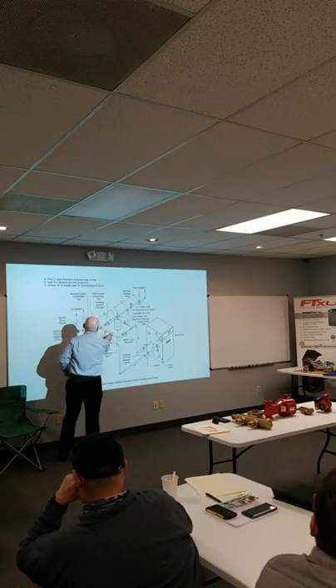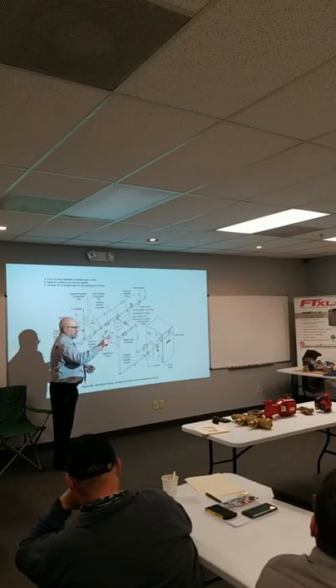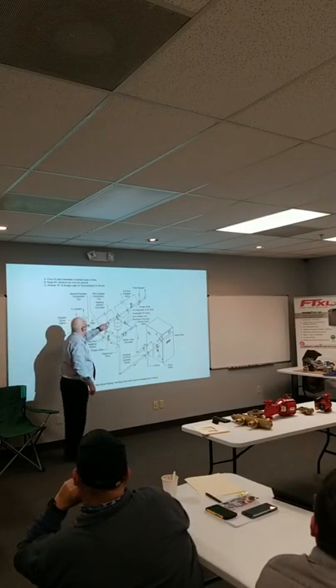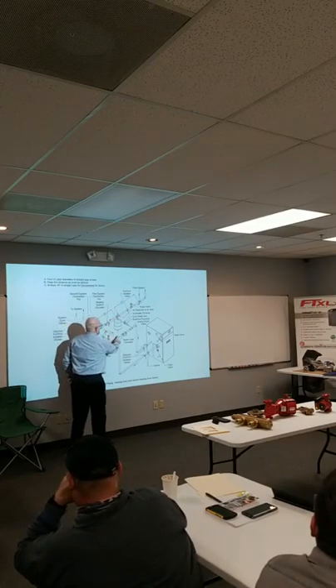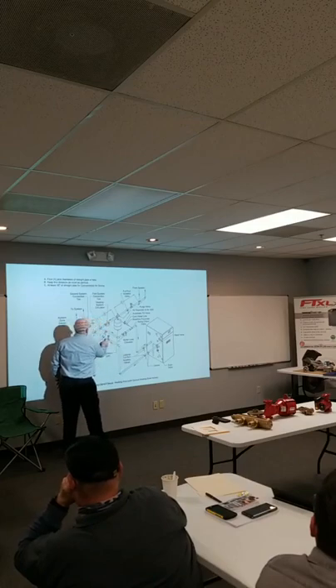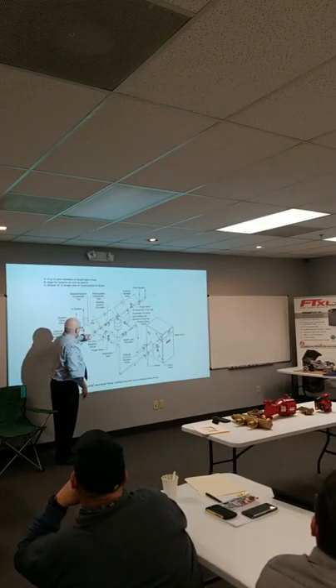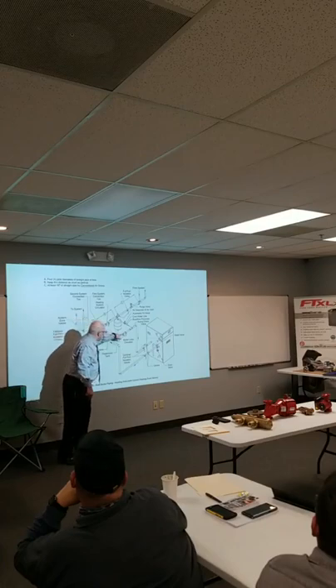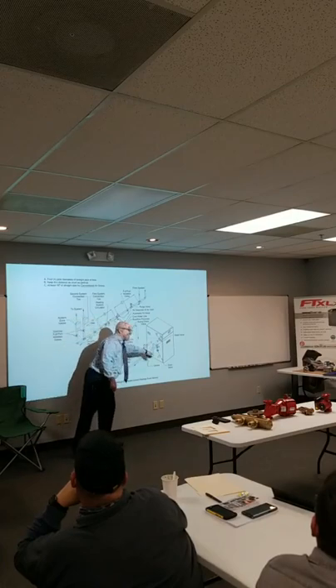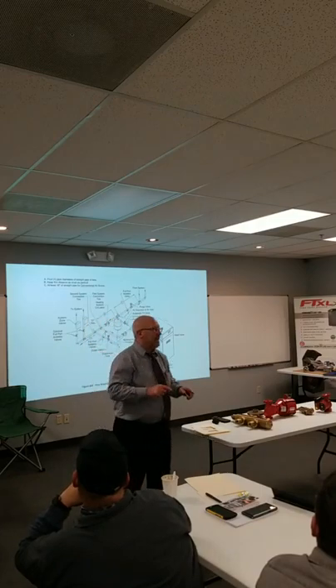So this is my return, okay? I did this on purpose, and this question kind of leads me to it. Because this is my return, I want my coldest water going back into my boiler. And I want to come out of my boiler and go this way. I want the system pump on the outlet side of my closely spaced T's. I want it over here. This pump, I usually want to pump into the heat exchanger. That's very important because they have a high pressure drop.